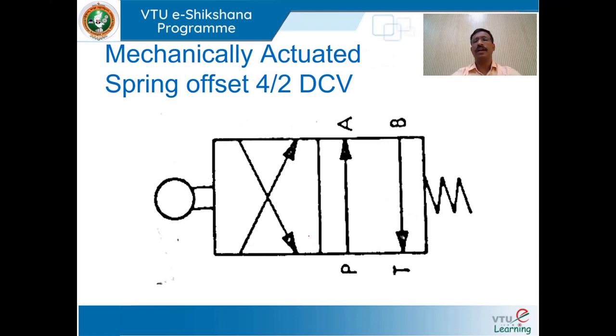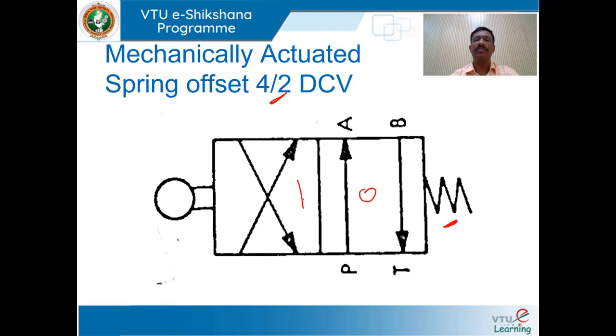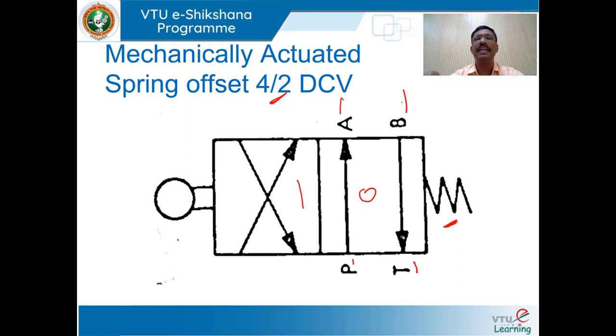We shall draw a symbol for a mechanically actuated spring-offset four-way two-position directional control valve. Two adjacent squares represent position O and position 1. Four-way: P connected to pump line, T to tank line, and A and B connected to the cylinder output ports. Mechanically actuated means roller operated.